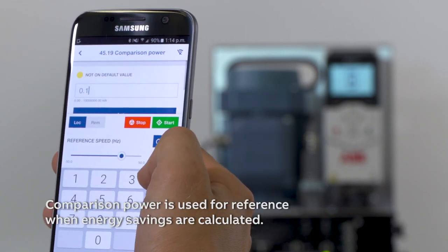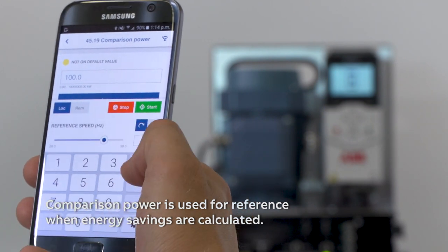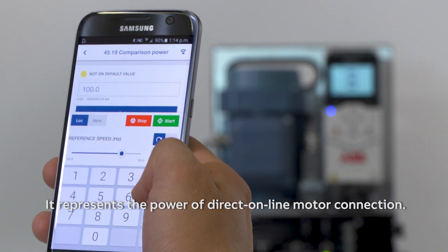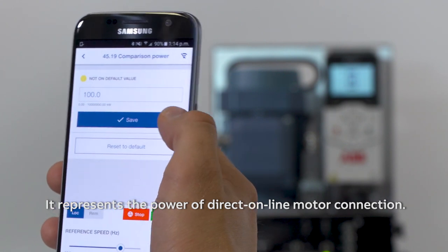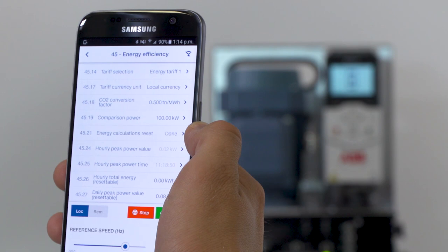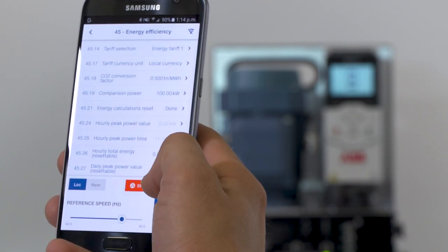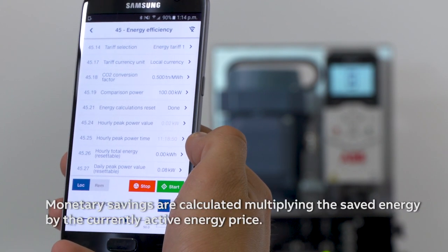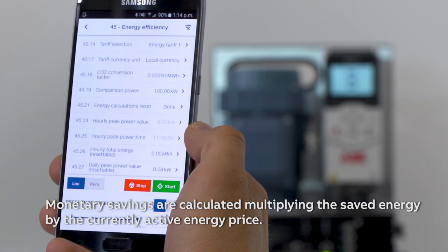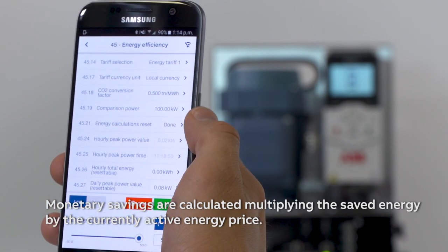Comparison power is used for reference when energy savings are calculated. It represents the power of a direct-on-line motor connection. Monetary savings are calculated by multiplying the saved energy by the currently active energy price.